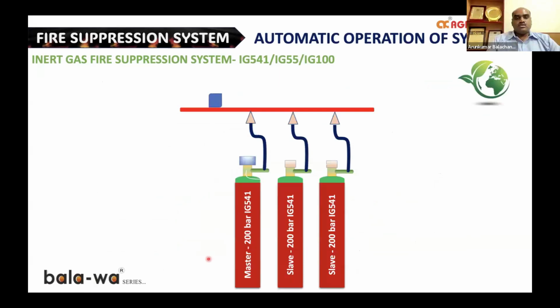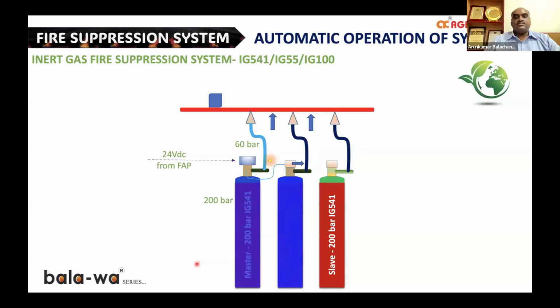I'm just going to show a small demonstration of what happens when a signal from the fire alarm panel is given to the inert cylinder. Once the master cylinder gets activated, similarly, it will give signals to activate the slave cylinders, and the gas from all the cylinders will go into the manifold, and it will go through the discharge pipes and nozzles. And the feedback from the manifold that the system has activated will go from a pressure switch. This is just a basic flow of things happening in an inert system.